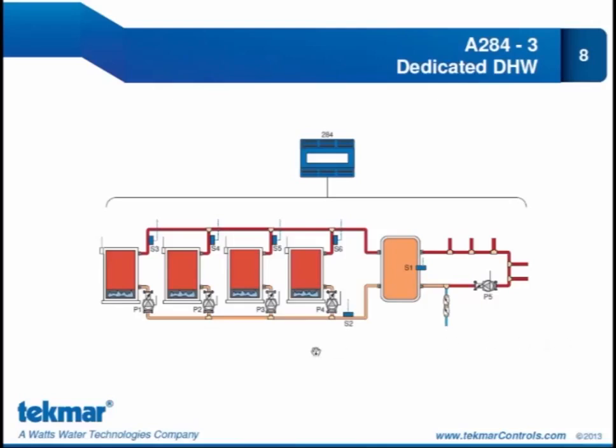Now this shows 4 on-off boilers. In this case, they happen to be 4 2-stage non-condensing boilers, and they're being operated to provide a fixed set point temperature for a dedicated domestic hot water load. In this case, we are operating a recirculation pump. Now on the control, we can operate either a recirculation pump or a combustion air damper. We use the same relay for both, so it has to be one or the other.